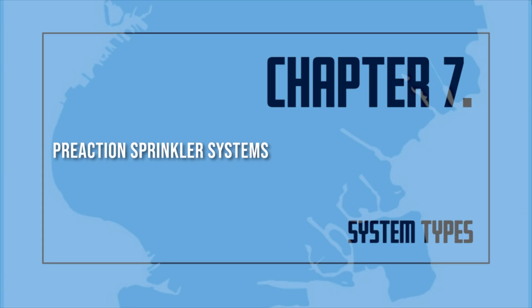The alarm signal is given as soon as the pre-action valve is opened. Heat-responsive devices are commonly used to trip pre-action valves. These devices are also used to activate alarm and supervisory systems. There are 3 main devices used to trip pre-action valves. 1. Devices designed to operate at a fixed temperature. 2. Devices designed to operate when the temperature in the room increases a set amount in a given time period, rate of rise, and 3. Devices combining fixed temperature and rate of rise devices.